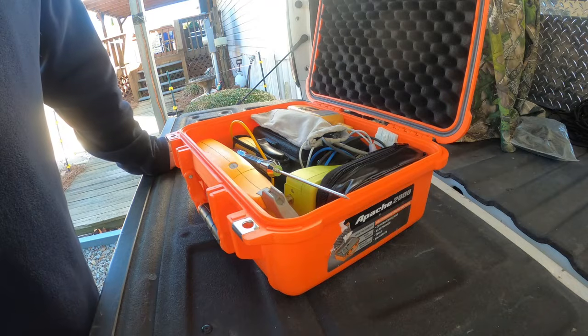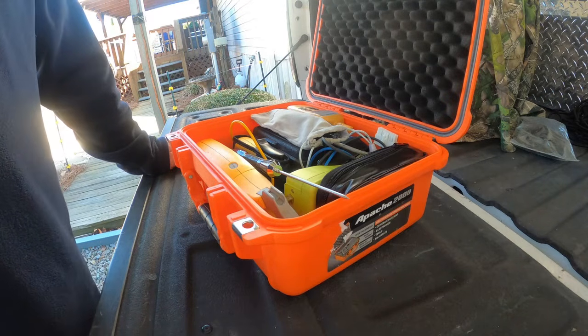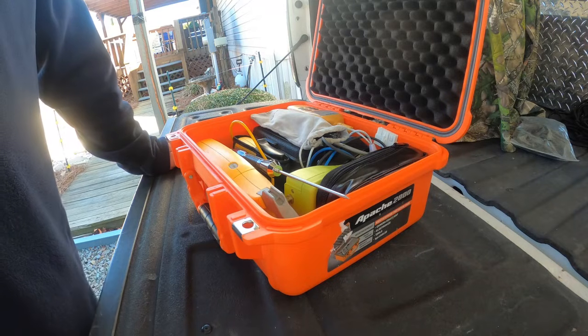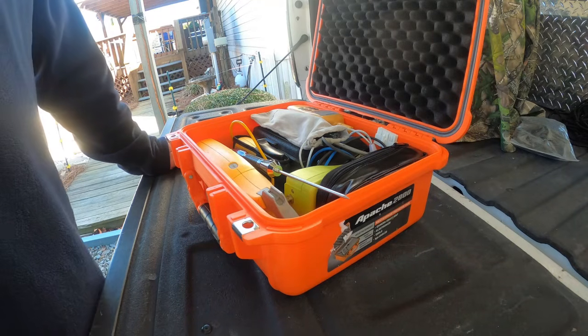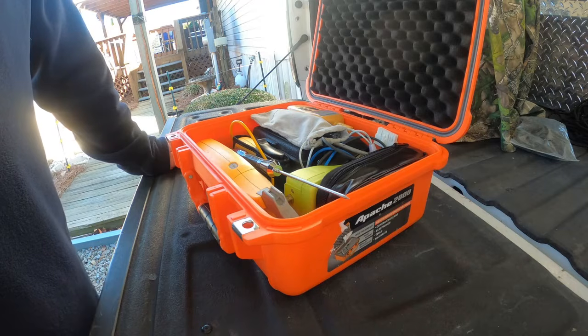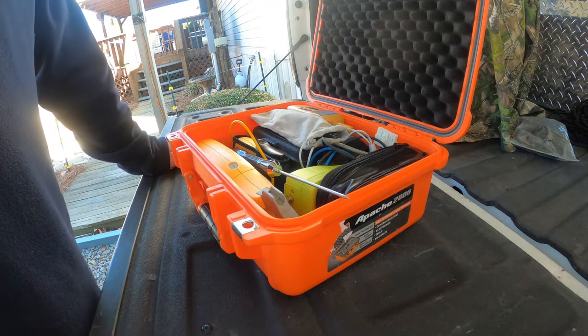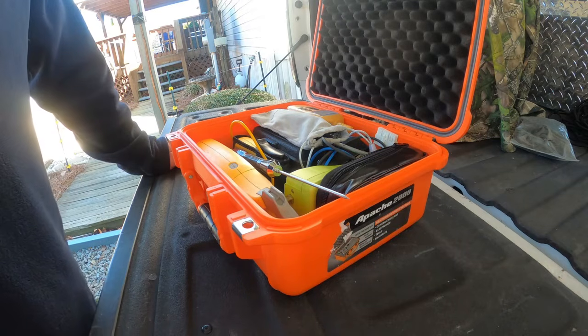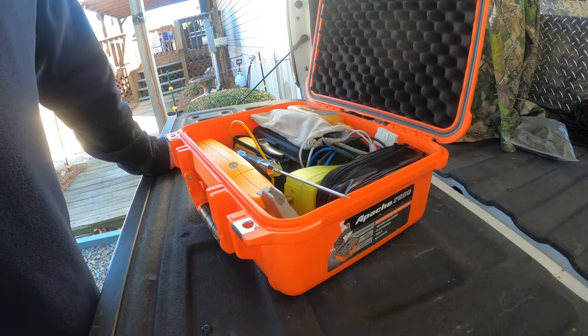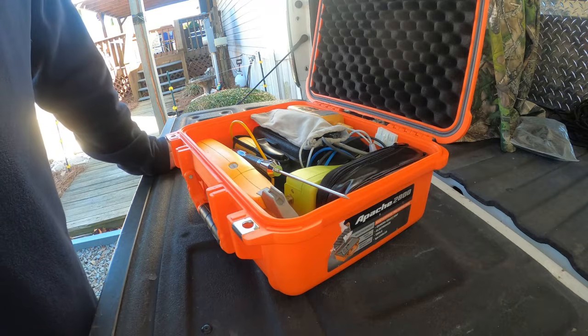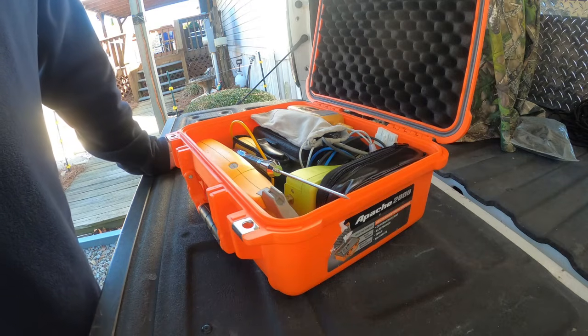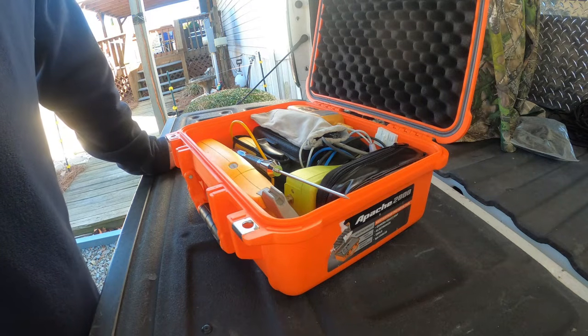check your static pressure on a system, especially if you're replacing one, because you can put in a brand new high efficiency system, but if your duct system's not properly sized and you've got airflow restrictions and you've got problems, that motor is actually going to ramp up higher to try to overcome that. And the adverse effect of that situation is that motor is now going to use more power, more watts. It's going to actually use more electricity, and their power bill can actually go up, even though you gave them a new high efficiency, more efficient system.